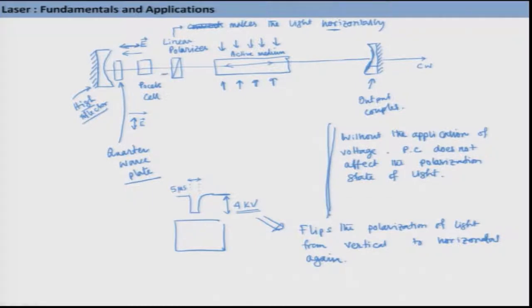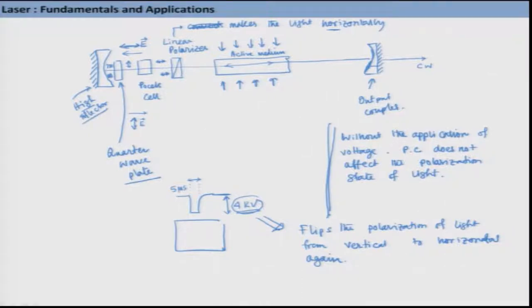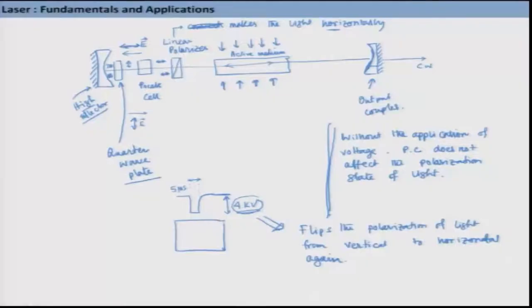So the light is horizontal here, goes through this element as circularly polarized light, and this circularly polarized light passes through and becomes vertical. When I apply this amount of voltage, it rotates the plane of polarization by 90 degrees again. This is possible only when I apply the voltage by a particular amount - in this case 4 kilovolt - which is generally used in Nd:YAG laser, a Q-switched Nd:YAG laser, just for your information.